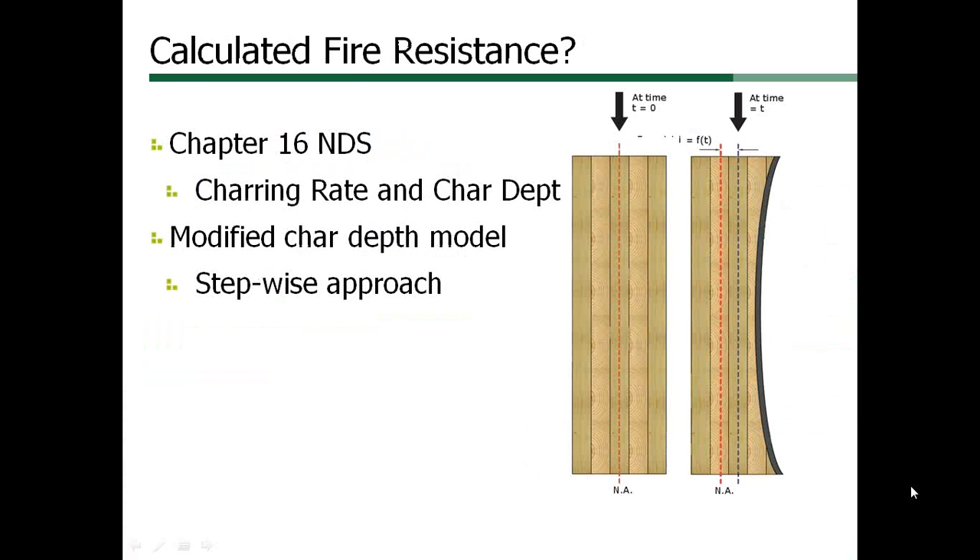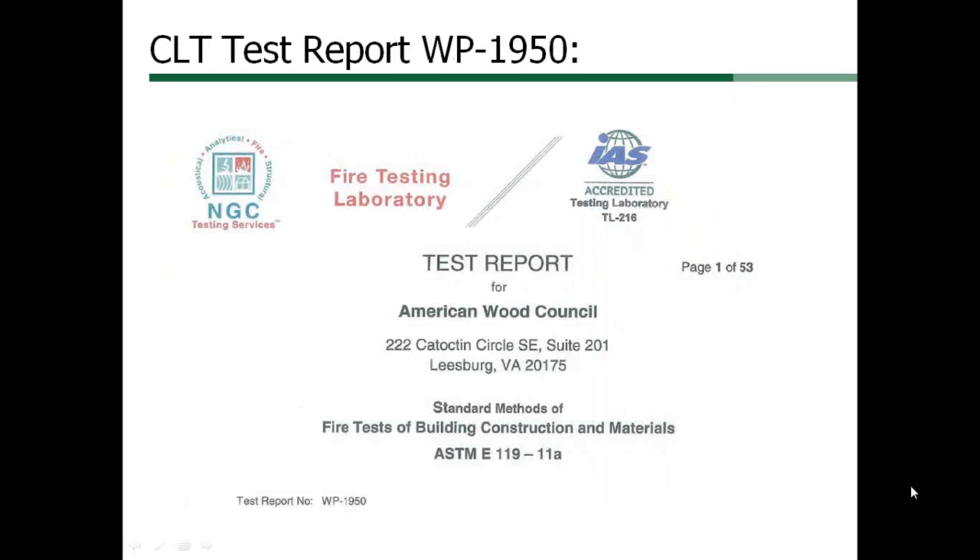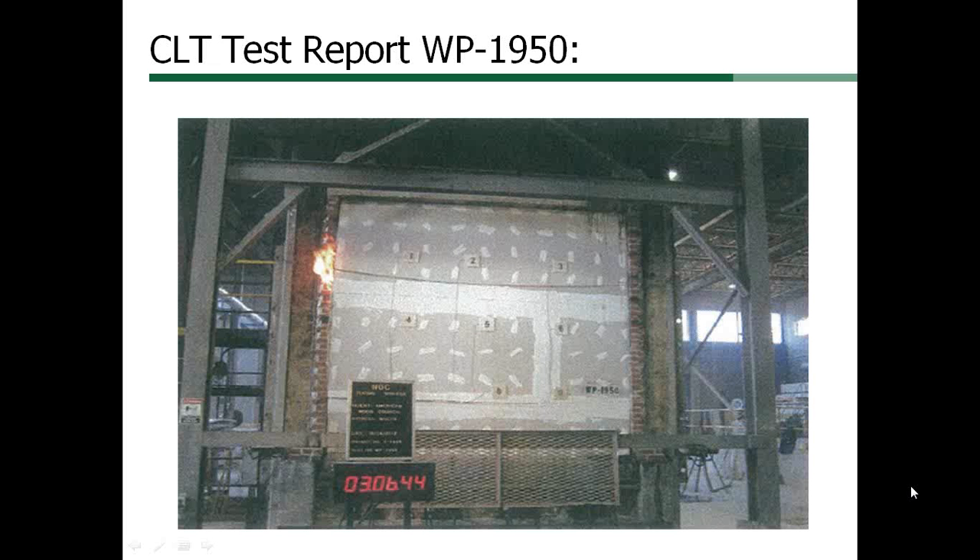CLT chars on the fire exposed side at an effective rate that is slightly faster than sawn lumber or glue laminated timber, depending on the thickness of laminations. This standard E119 wall test was on a 5-lamination, 6-7/8-inch thick CLT wall with one layer of 5/8-inch Type-X gypsum board each side. It was loaded with 87,000 pounds of vertical load throughout the test and failed at 3 hours and 6 minutes.